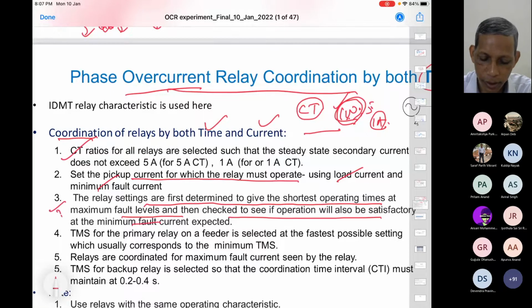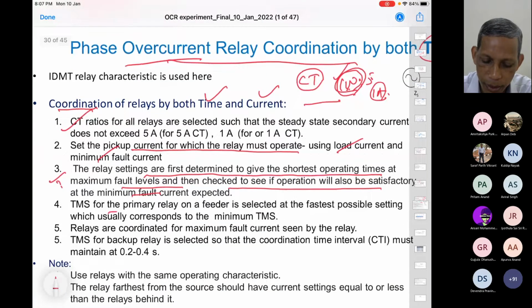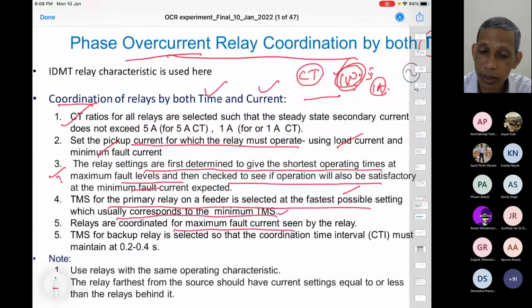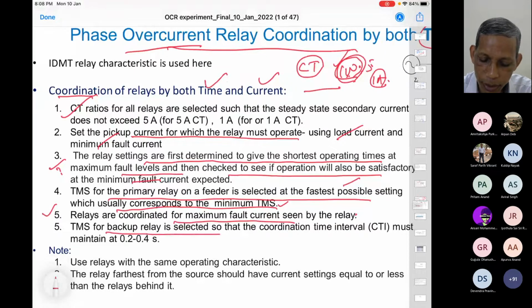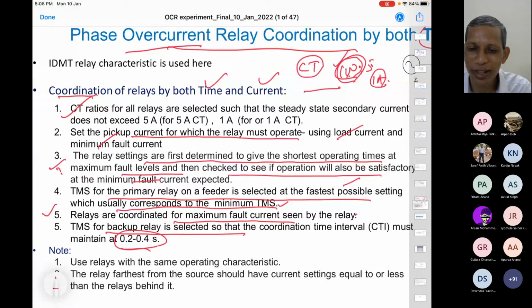This is important. The TMS for the primary relays is selected to be the fastest possible, usually corresponding to the minimum TMS. Relays are coordinated for the maximum fault current seen by the relay, not for the minimum fault current. The TMS for backup relays is selected based on a coordination time of 0.2 to 0.4 seconds. That is the 10 cycles to 20 cycles I was telling you.